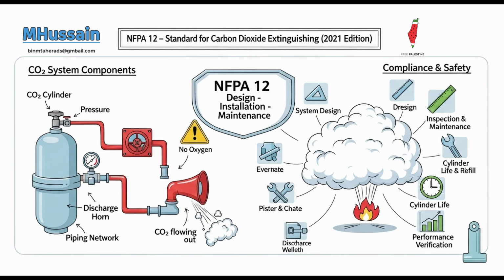The reignition risk. If there's a persistent ignition source, such as an electrical arc, residual heat in equipment, a smoldering hotspot, or a deep-seated fire within solid combustibles, the fire can easily recur once the CO2 agent dissipates. So the gas floats away and boom, it starts again. Potentially, yes. The extended duration ensures that the fuel cools below its auto-ignition temperature, or that any hidden embers are fully suppressed, preventing a reflash. It's about ensuring the fire stays out. That's a crucial detail. A fire isn't truly out until it's cool.